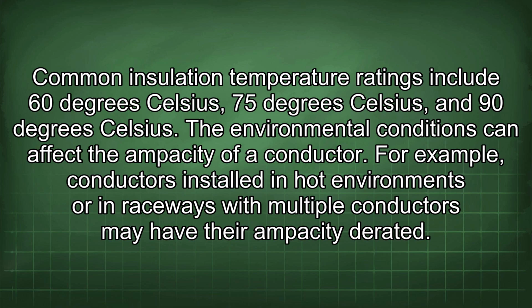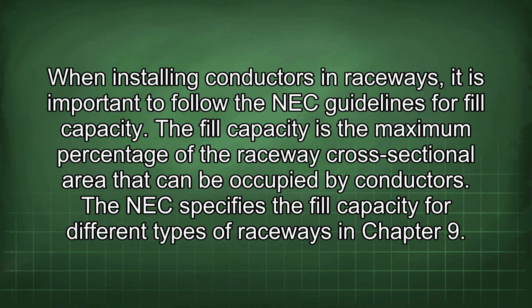The environmental conditions can affect the ampacity of a conductor. For example, conductors installed in hot environments or in raceways with multiple conductors may have their ampacity derated. When installing conductors in raceways, it is important to follow the NEC guidelines for fill capacity. The fill capacity is the maximum percentage of the raceway cross-sectional area that can be occupied by conductors. The NEC specifies the fill capacity for different types of raceways in Chapter 9.